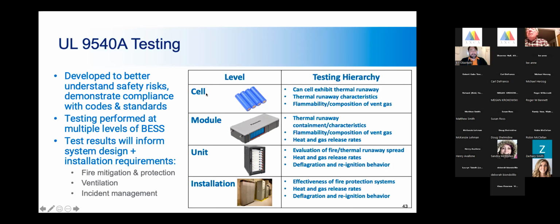The UL 9540A test, as you can see in the second bullet, is performed at multiple levels. Remember at the beginning I told you to keep in mind the cell, the module, the unit - I did that for a reason. There is a different test at the cell level, so there's a 9540A for the cell, for the module, for the unit, and then an installation-level 9540A test as well. So we have nationally recognized testing laboratories testing these systems at every level to see what happens in the event of thermal runaway. Those test results then inform system design and installation requirements - chief among them fire mitigation and protection requirements, ventilation requirements, and incident response as well.